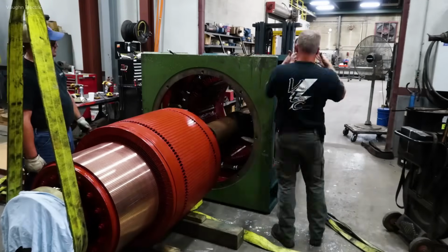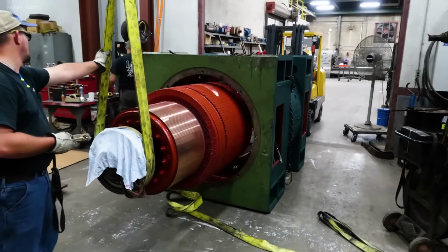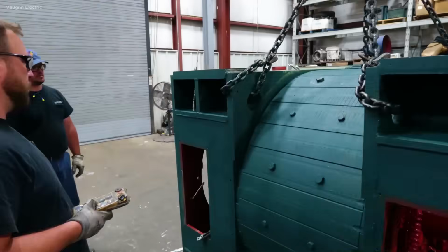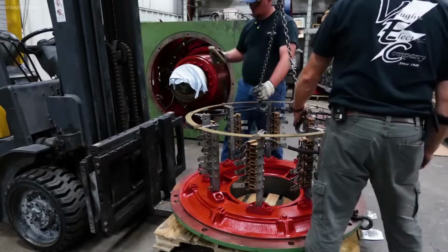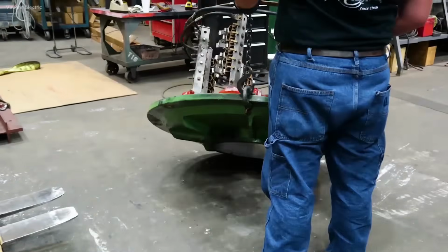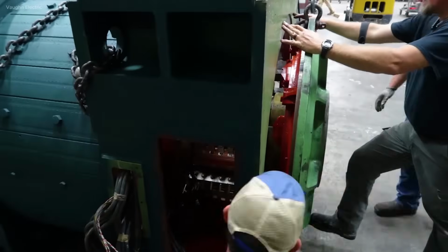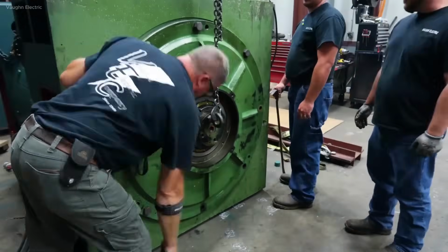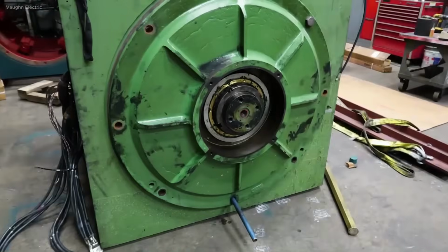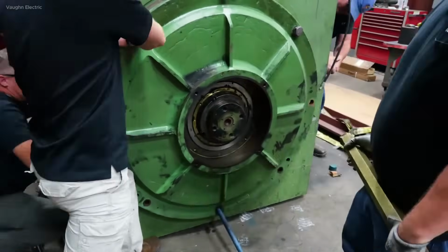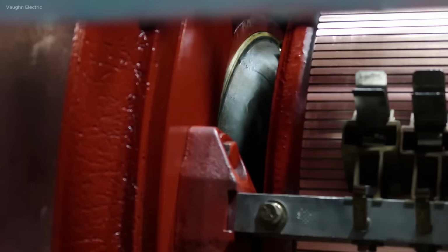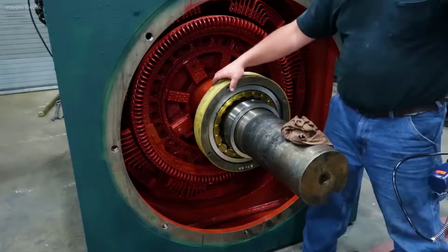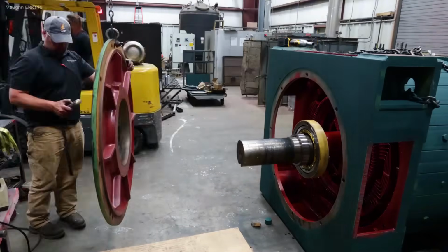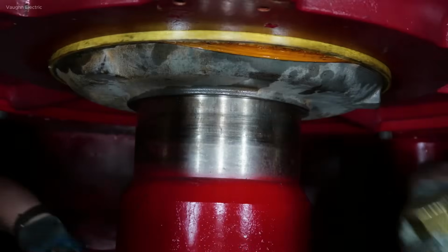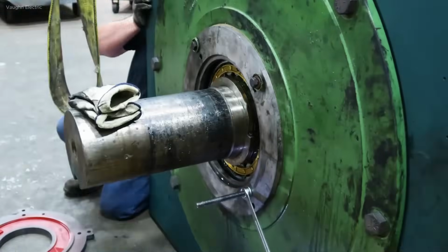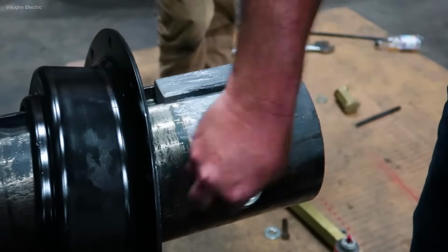Reassembly begins by installing new bearings, typically double-shielded or open type depending on application. Bearings are heated to approximately 230 degrees Fahrenheit using an induction heater before being mounted to prevent shaft damage. The rotor is carefully aligned and inserted into the stator using hoists and alignment tools to avoid contact damage. End bells are mounted, and all components are torqued to manufacturer specifications. Rotor-stator air gap is measured to confirm proper alignment.